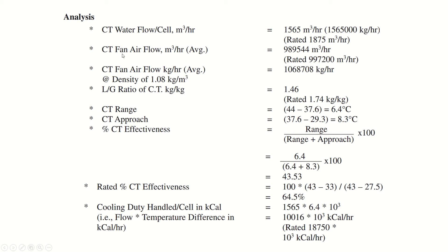The cooling tower fan air flow of 989,544 m³/hr is multiplied by the air density of 1.08 kg/m³ to get the air flow rate as 1,068,708 kg/hr. The L/G ratio is the ratio between water flow rate and air flow rate. Dividing these two flow rates gives an L/G ratio of 1.46.